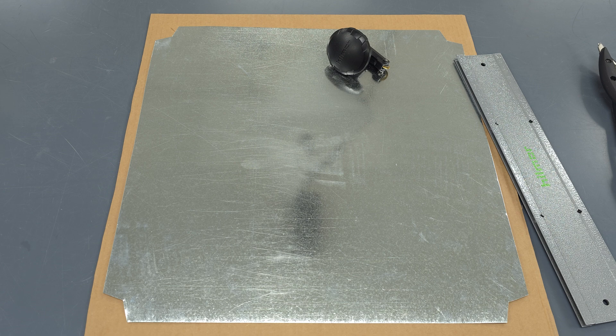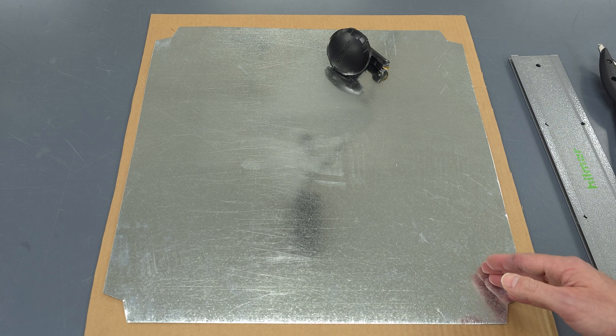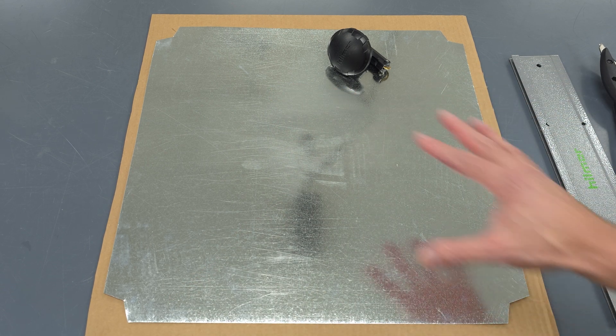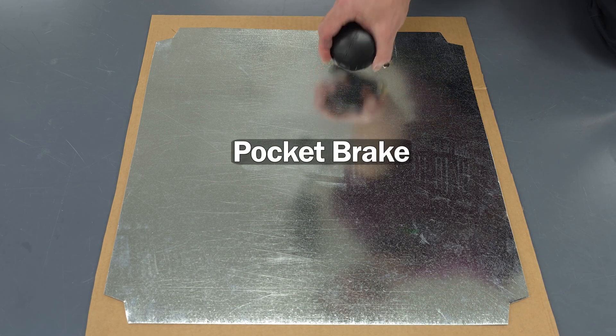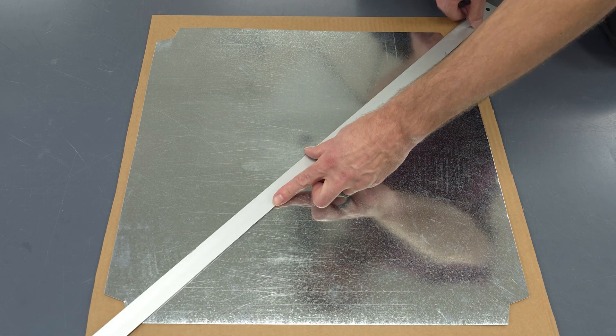The next thing we need to do before using our tool is make our bends in the metal — they're called cross brakes. When the air pressurizes the duct, the object is for the sheet metal to not make a popping noise. To do that, we can use our Hilmor pocket brake. This is one way of making cross brakes.